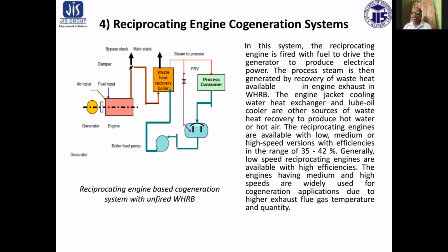The reciprocating engines are available with low, medium, and high speed variations with efficiencies in the range of 35 to 42%. Generally, low-speed reciprocating engines are available with high efficiencies. The engines having medium and high speeds are widely used for cogeneration applications due to higher exhaust flue gas temperature and quantity.